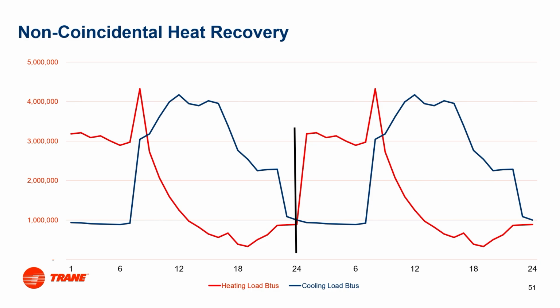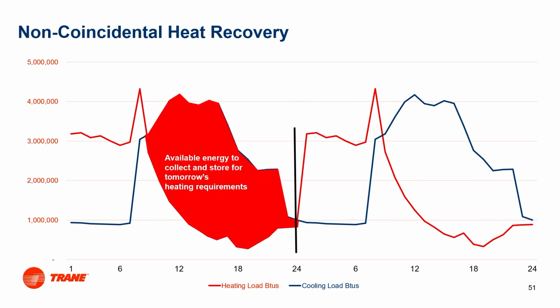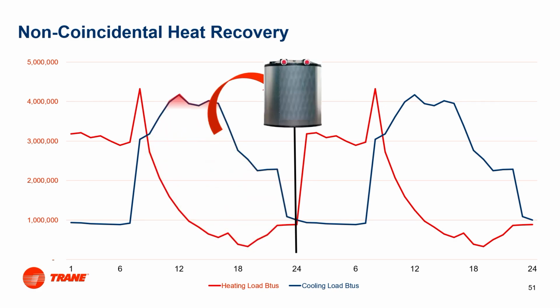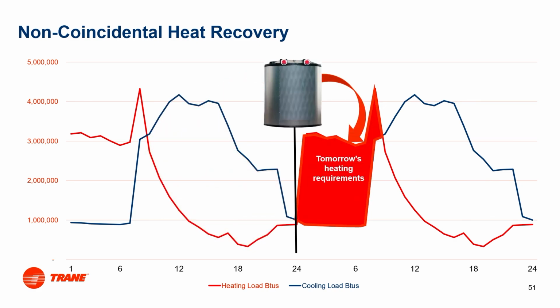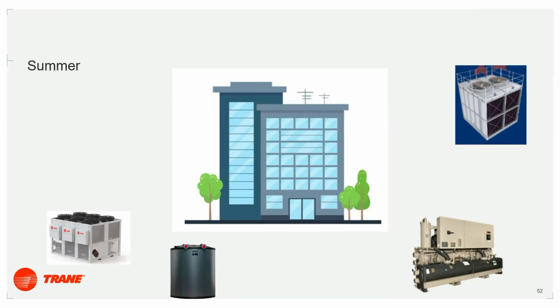Now, most of the time we're handling it with air side economizer. We crank that down, then we're going to be able to keep those BTUs in the building. But if we don't have any place to store those, we better be doing air side economizer, otherwise we're running a chiller for nothing. So what if we actually use that heat, stored that heat, to heat our building the next day? Geothermal is a great example of this, but what about thermal storage, thermal batteries? If we use this in the form of a thermal battery, we can store that heat for use the next day. So we're talking about ice storage here.